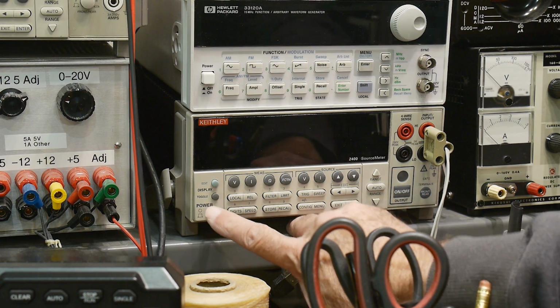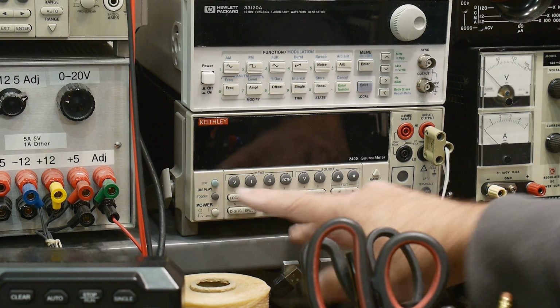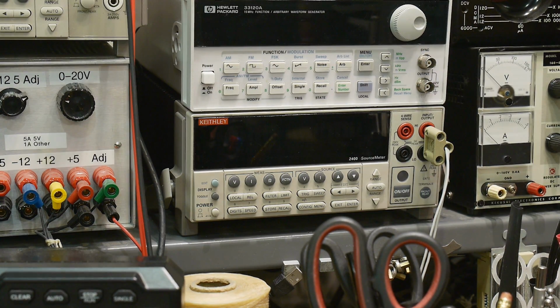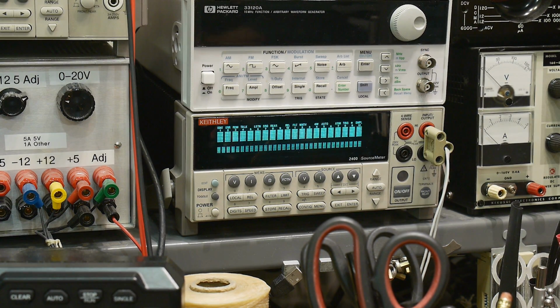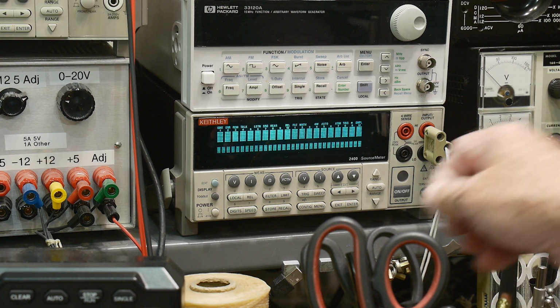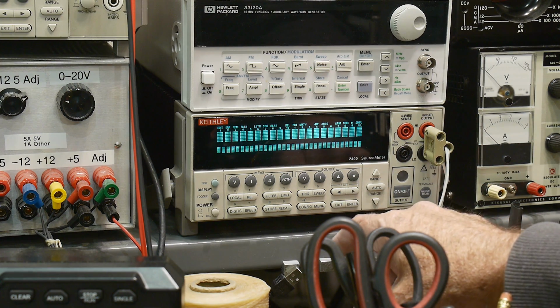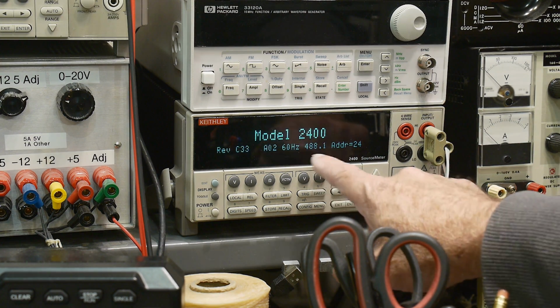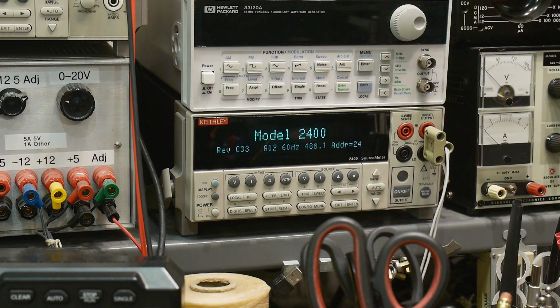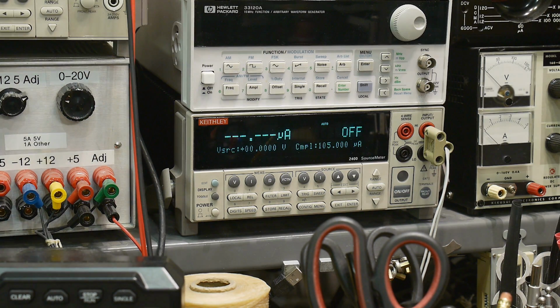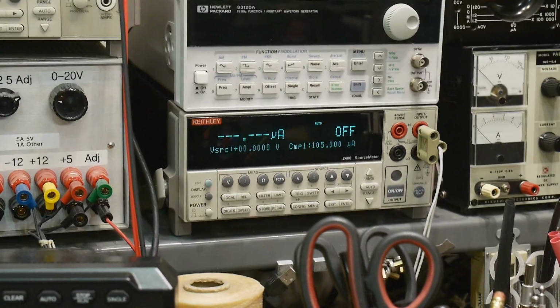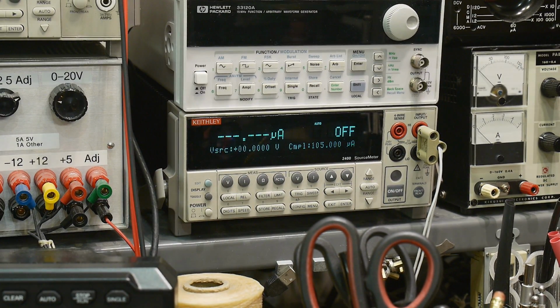Now, when you power up the instrument, most instruments in the lab will do this if they're GPIB controlled. They'll tell you what address they're at when they wake up. And this one says it's at address 24. So it says 488.1, address 24. Okay, so now we need to connect it.